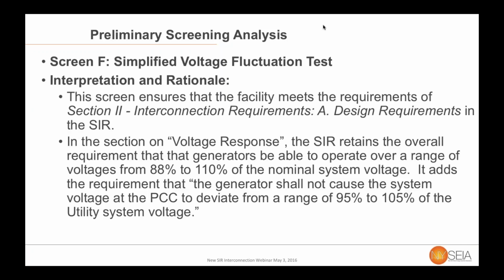The intent of this screen is simply, again, to implement one of those requirements from the design requirements section. So in Section 2, under the design requirements, the voltage response notes that the facility has to be able to operate over the same range as before, 88 to 110, but it's added now this language that it shall not cause the voltage to deviate outside of the 95 to 105 levels.